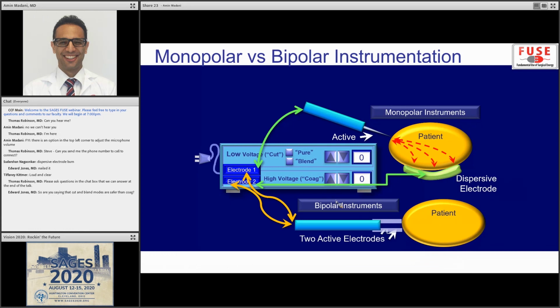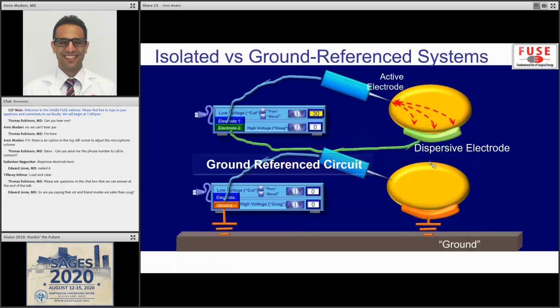Bipolar instruments, you have two active electrodes. There's no such thing as a dispersive electrode. So when you activate it, the current passes through, but the good thing here is that the path is restricted, so there's less areas the current can go to cause problems. Now, does it mean bipolar instruments are the answer to everything? No. Monopolar devices are very useful, very flexible and very handy to use, but it's just about understanding how to minimize this current that could cause other issues. And like I said, grounding pads, we don't do that anymore. So it's important not to call it that.